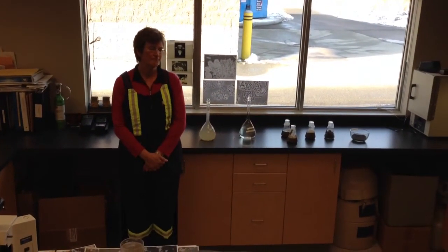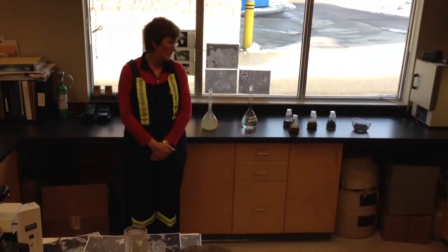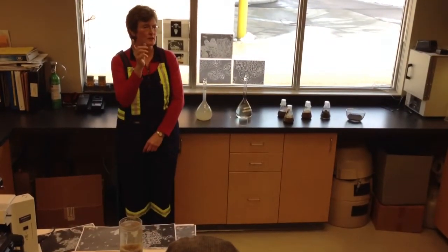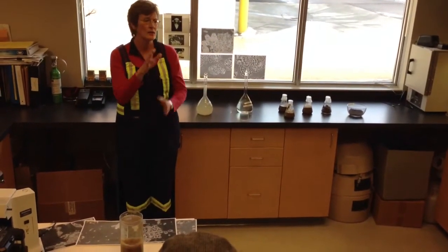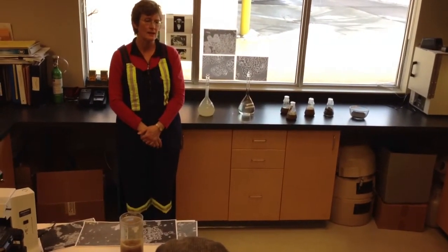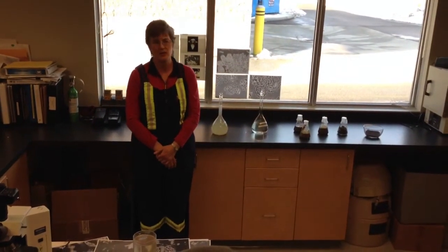Katie, what would the normal BOD and TSS be on the effluent going out? Normally, our regulation is 25, but we're usually less than 10. That's the detection limit pretty well. We are usually less than 10, and our total solids are about 10 too.